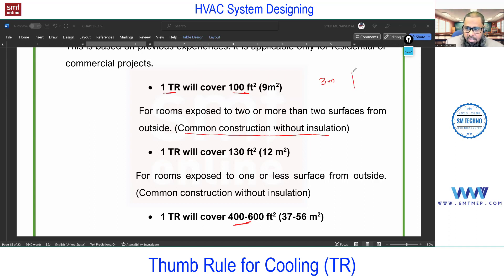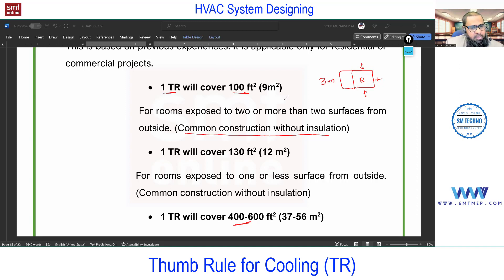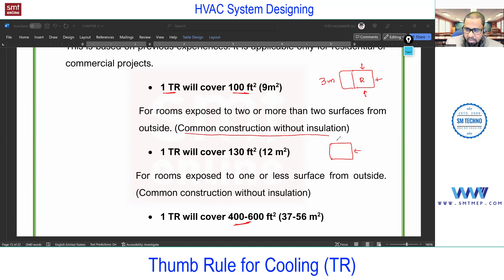One TR covers 100 square feet at a standard 10-foot height when more than two sides are exposed. For example, consider a room in top view: if three sides are exposed to outside and only one side has an adjacent room, then for a 100 square foot room, one ton is required. If the room is 200 square feet, consider roughly 2 TR. If the room has only one exposed side with other rooms on the remaining sides, one ton can cover up to 130 square feet.